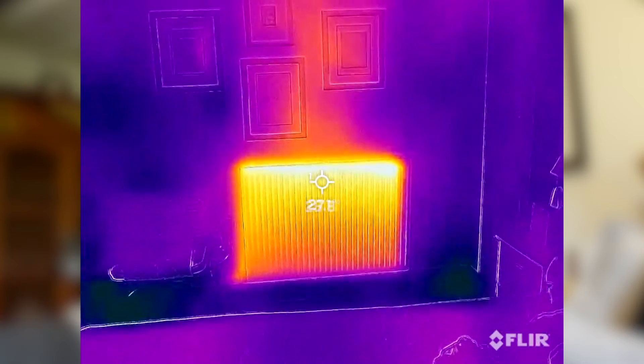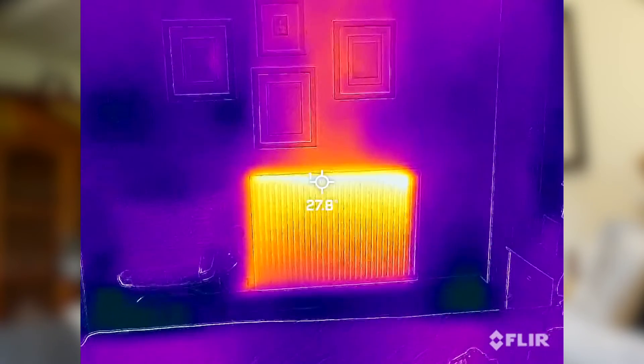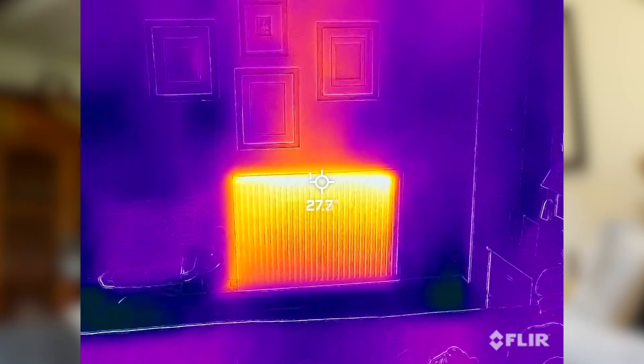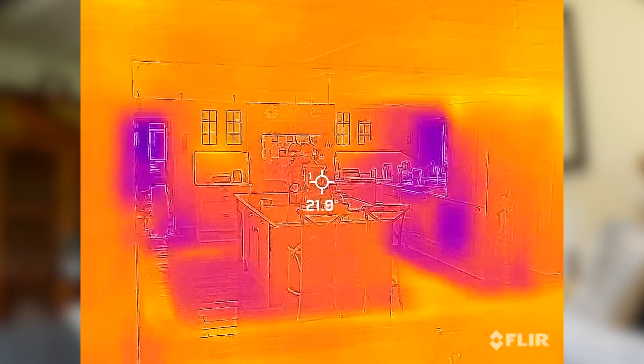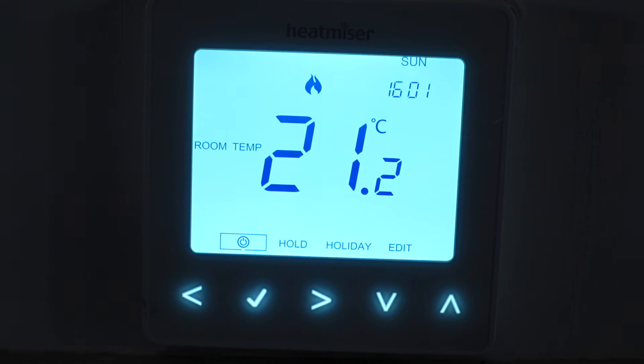It is important to highlight that with weather compensation activated, the radiators only feel slightly warm when you touch them. In contrast, when the system runs at 45 degrees centigrade, they are noticeably warmer. Despite this, the rooms all feel adequately warm and cozy, with most thermostats reading at least 21 degrees centigrade, all while running at about half the previous costs.